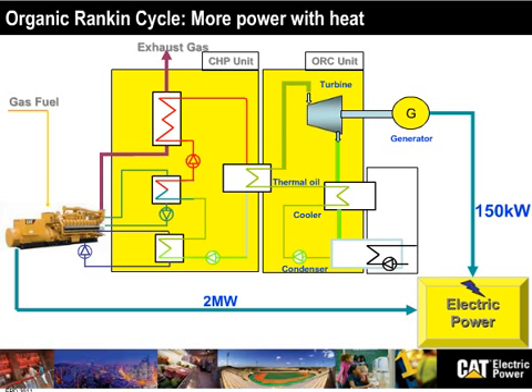I've seen it in landfill applications. It's becoming more and more popular in landfill applications too, where there is no heat need, and they want only power, and you can sell that power, or there is regulation where you need to use all of your gas, and if you have extra gas, you don't want to flare it, so you burn that gas in a boiler that you insert in the ORC. So that's a typical trend.